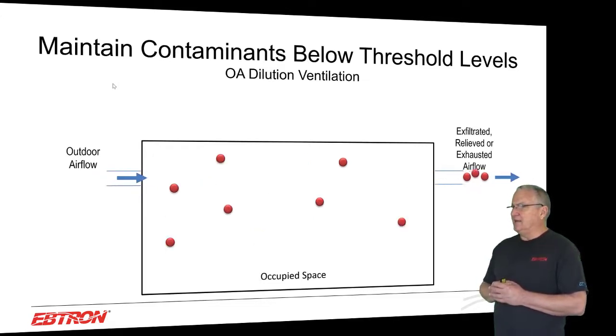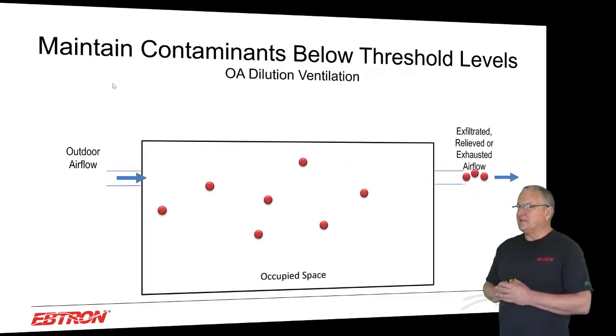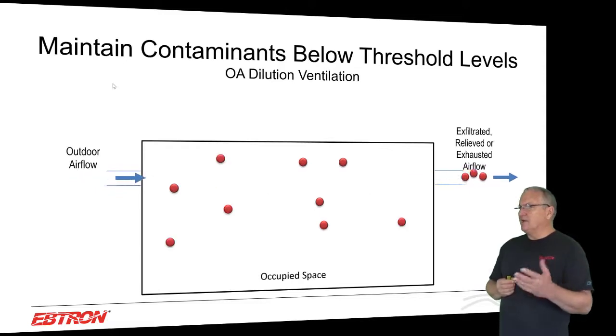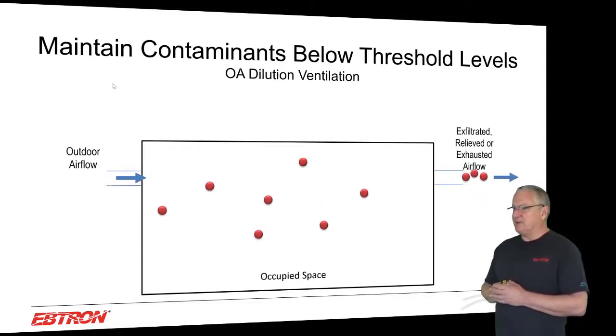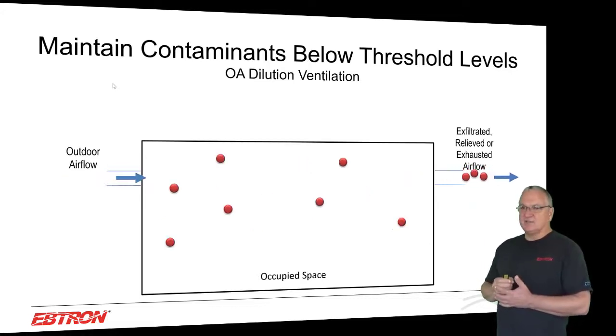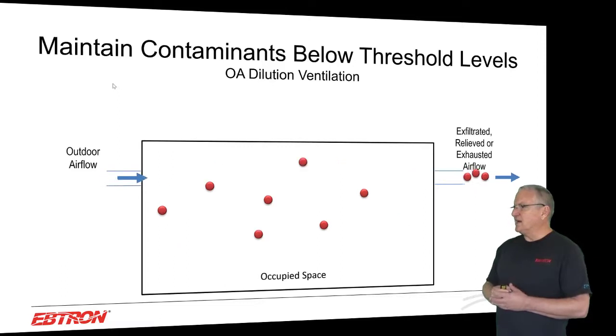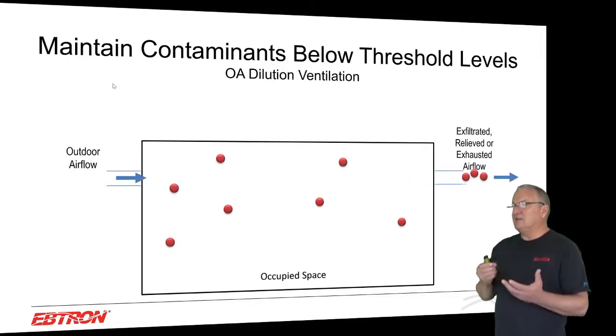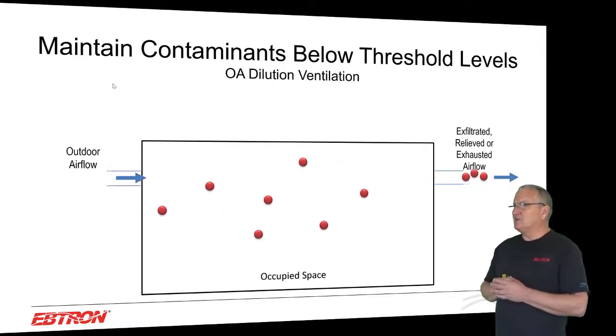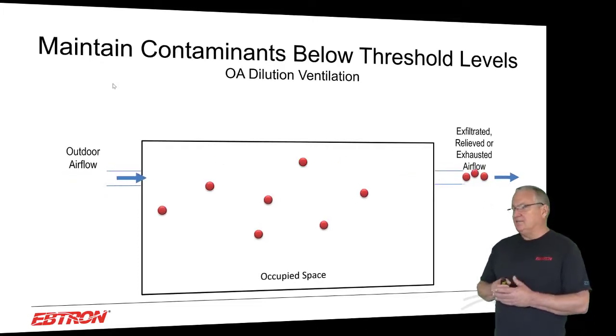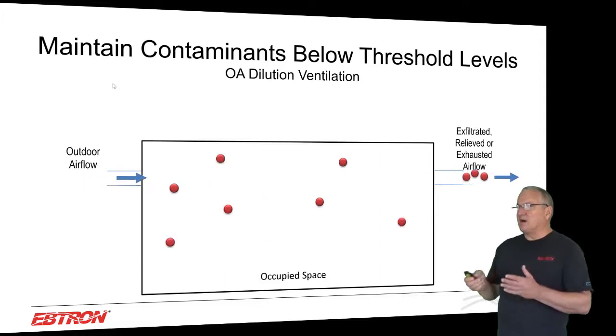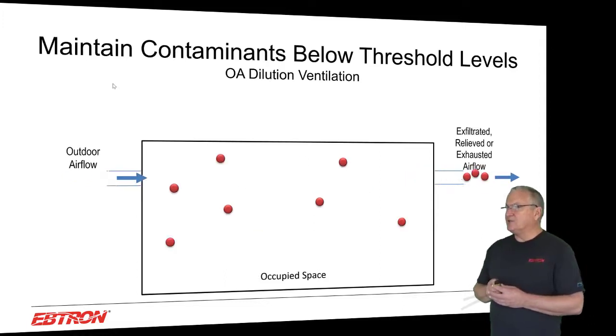What we can do is dilute it. We take outdoor air, bring it into a space, and it's going to dilute whatever contaminants are in the space, including COVID. They'll either be exfiltrated or exhausted out of the building, and you will reach some type of steady-state level of contaminants by bringing in outdoor air. The question is really what the proper amount of outdoor air is.